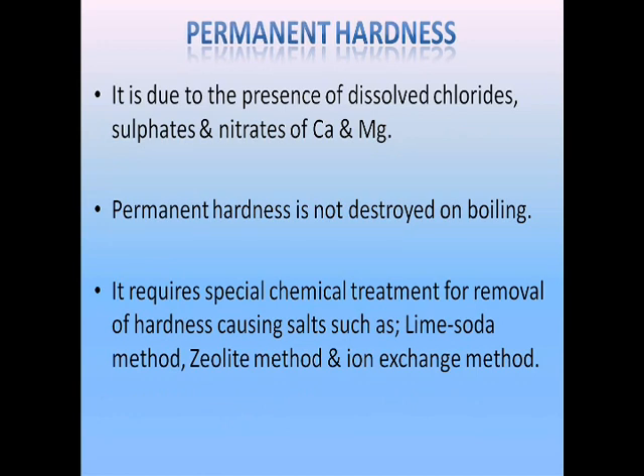Permanent hardness is due to the presence of dissolved salts of calcium and magnesium such as chlorides, sulfates, and nitrates. Such salts cannot be removed by simple techniques like boiling or filtration. Hence it is called permanent hardness, and it requires special chemical treatments to remove such salts, like the lime soda, zeolite, or ion exchange method.